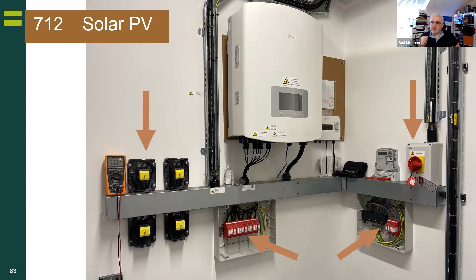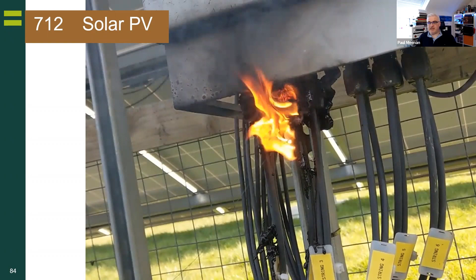I don't really trust the plugs. Sometimes the plugs can go wrong, and sometimes the installations can go wrong and the strings can melt. There are also requirements for consideration of sizing of DC cables, protection against mechanical impact, UV degradation, etc. So solar PV is leveled up. It's very specialist, but it's worth knowing because it's here to stay.